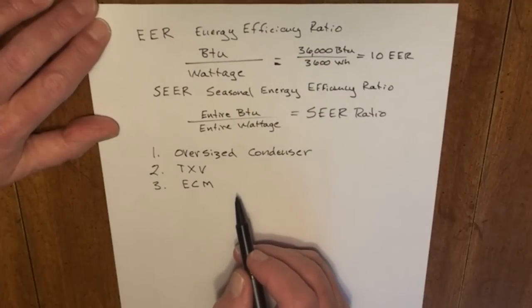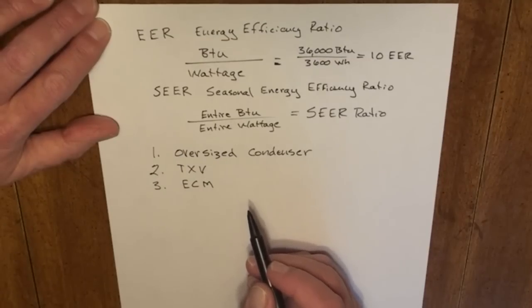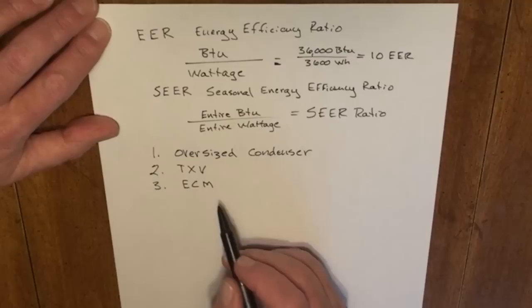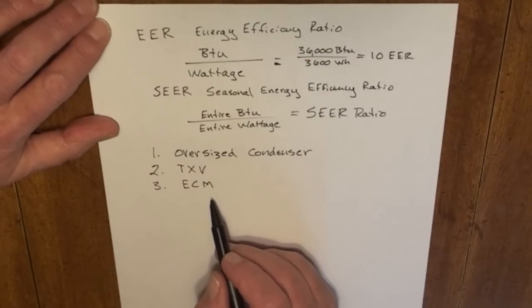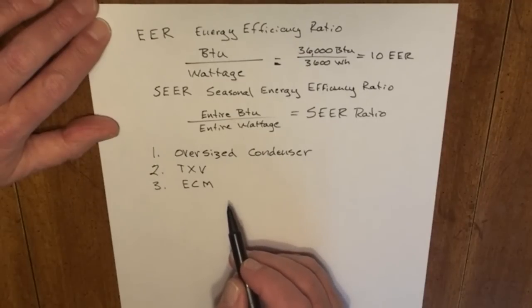It makes it more efficient because if you don't need, say, two tons of airflow within your house to achieve our 450 CFM per ton, this can adjust for it. Another thing about the ECM motor is it can give us greater control over humidity within the structure.